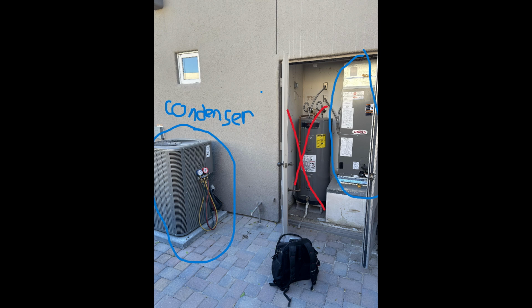Just want to return to this picture one more time and close out here, I think, and end at a very high level and hit some stuff. The condenser rejects heat outside. That's why the top of those condensers are hot, because it's rejecting heat, and it should be hotter. It should be rejecting air hotter than what it is outside. So I'm in Phoenix, Arizona. If it's 105 degrees outside, it should be about like 110, 115 degrees of hot air blowing out of the top of that condenser.